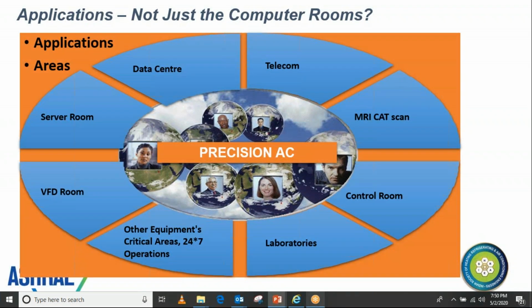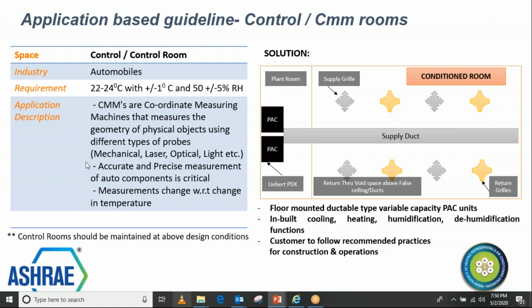We'll go into a little more detail on how these applications are different, and study them more in terms of temperature and humidity requirements. So in control rooms and CNC rooms, in CMM rooms, these kinds of rooms, the temperature requirement is typically a little wider range, like maybe 22 to 24, plus or minus 2, or plus or minus 1. But it is not just the temperature, as I said. It is not just the impact of the failure of the component. Obviously, this matters, as we discussed in the previous slides. But in addition to this, the cost of the power, the cost of the life cycle, the cost of the overall downtime, the many costs involved make the precision AC system the first choice for all the applications.